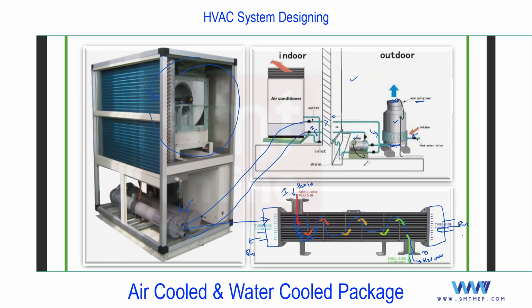In case of a water cooled chiller, the case will be different. You'll find higher capacity. And remember, the same concept for the condenser you'll find in a water cooled chiller also. This will help you when we deal with the water cooled chiller. And in an air cooled chiller, you'll find a shell and tube evaporator. So the shell and tube heat exchanger you'll find in an air cooled chiller as well as in a water cooled chiller, for the condensing side as well as for the evaporator side. So this concept will help you. At this level, I'm just giving the reference.